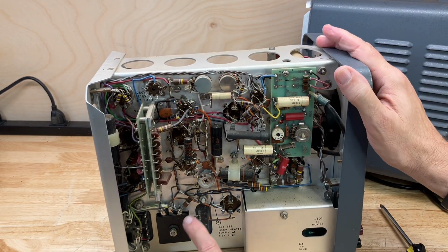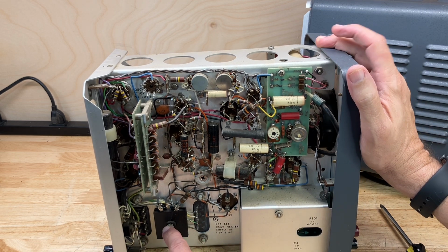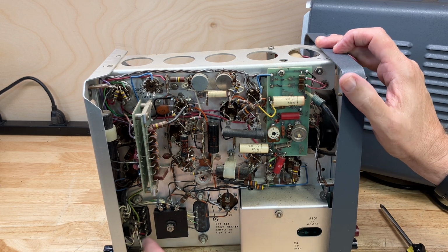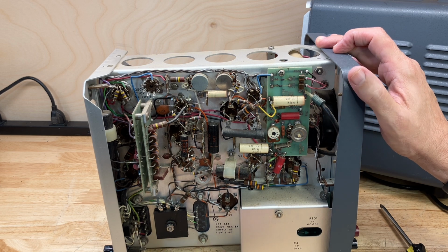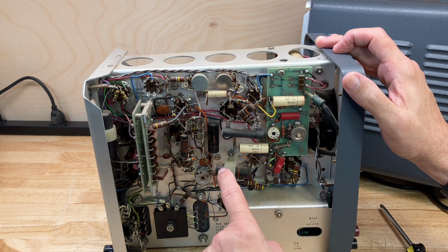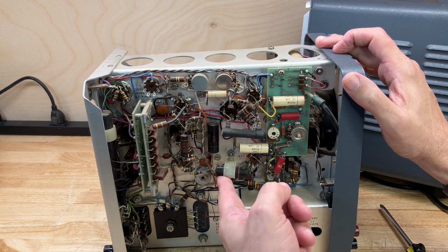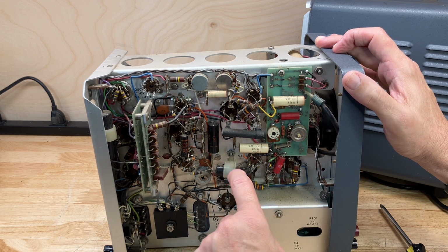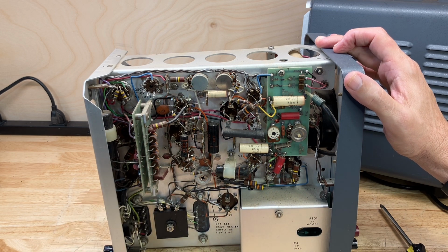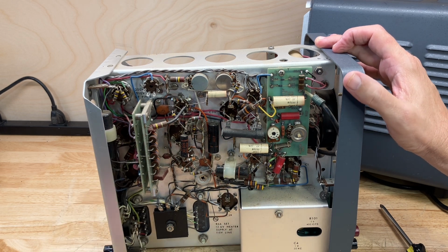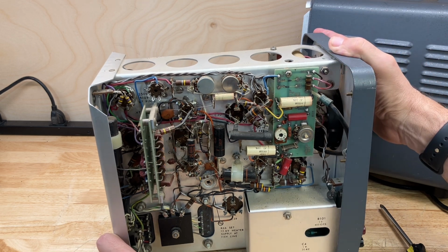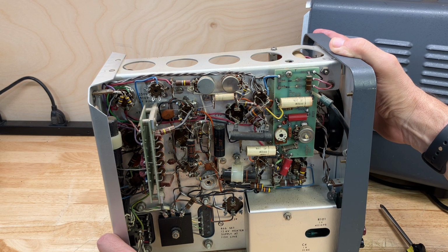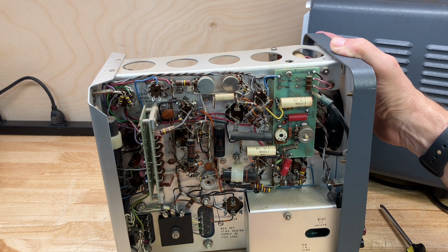Okay, there's one thing I see here that I might want to look at replacing: the selenium rectifier. Clearly it's working, so I don't have to immediately replace it, but that might be something I want to look at. We have these Bumblebee or Black Beauty style capacitors, a couple of them in there. I will test them for leakage, but I'll bet they're okay as well. HP in general did not use cheap components, especially back then. So we might not have to do any servicing at all to this instrument, besides blowing the dust out and cleaning it up a little bit. I'll probably end up replacing the selenium rectifier with a silicon one, 4 diodes or something. We'll take a look at that.